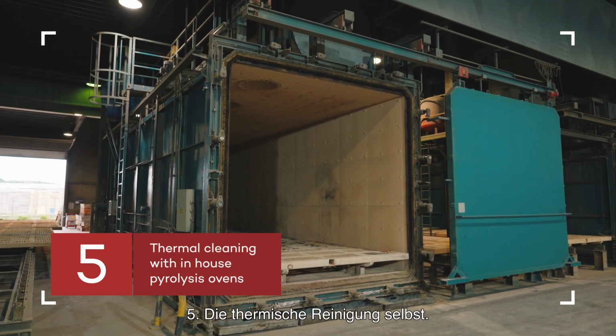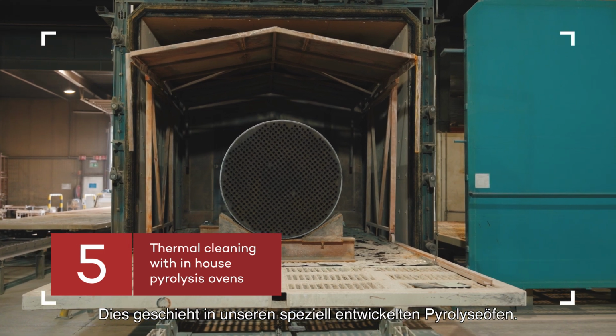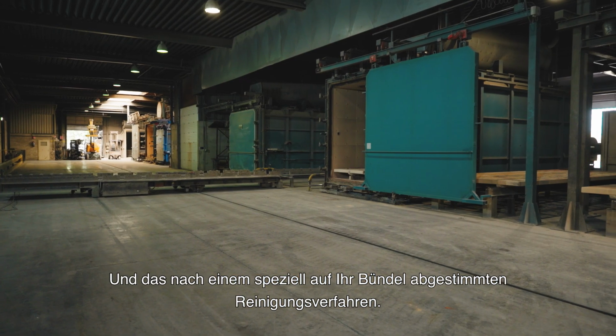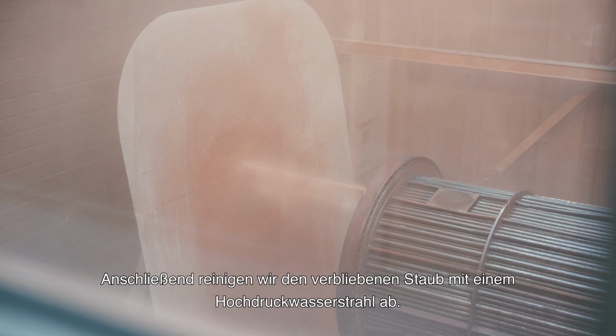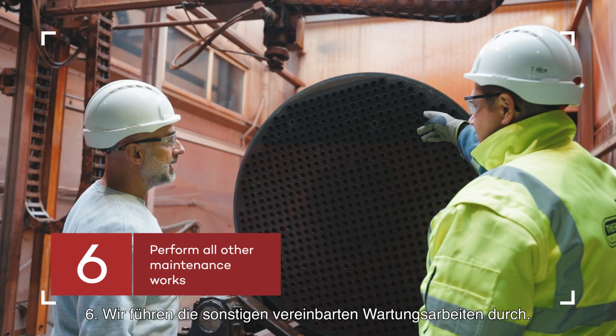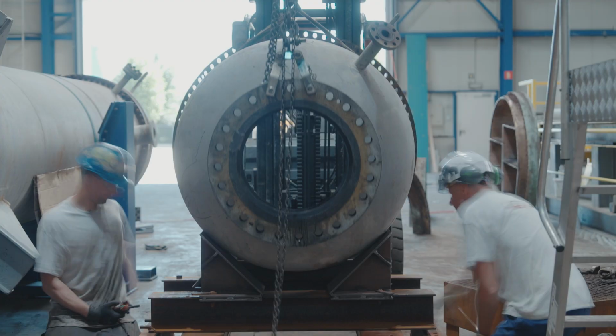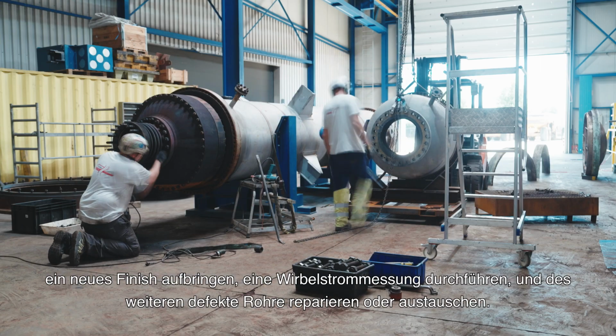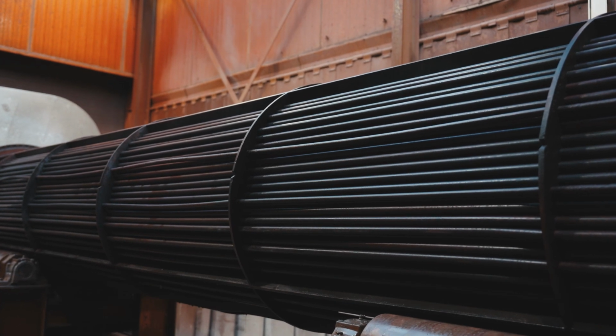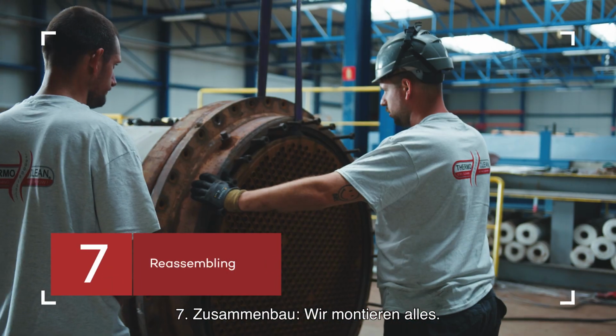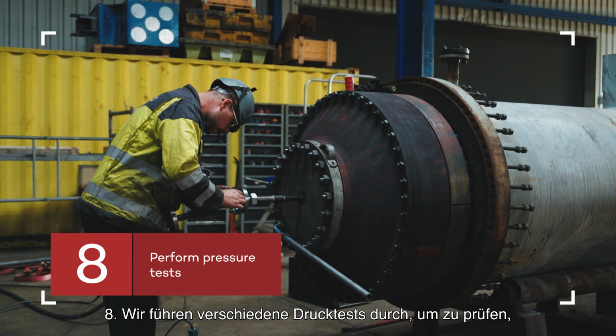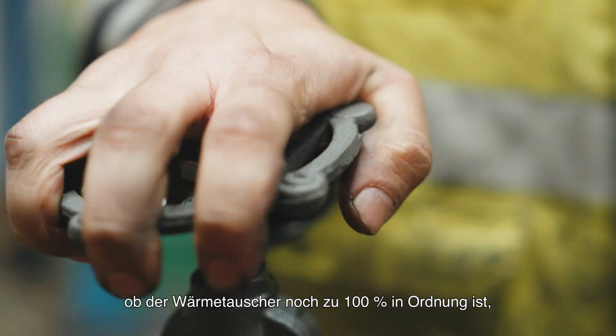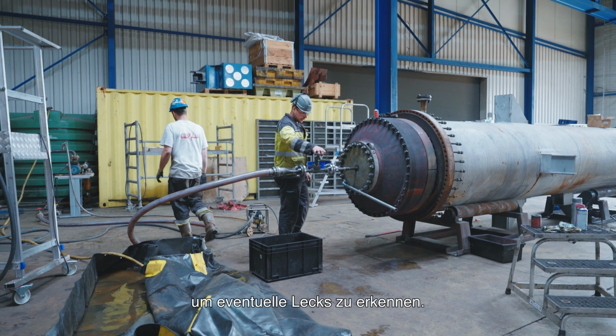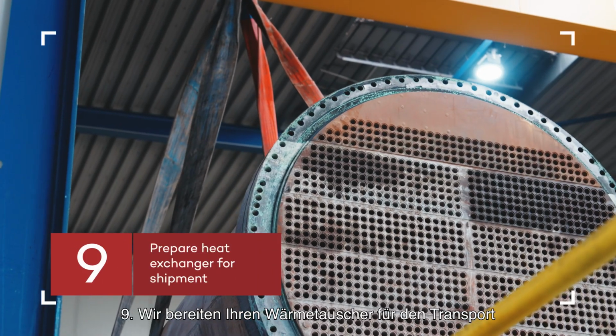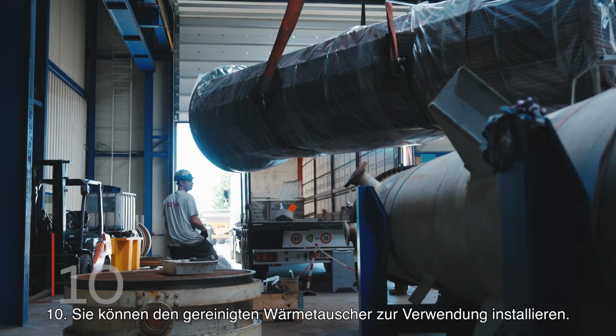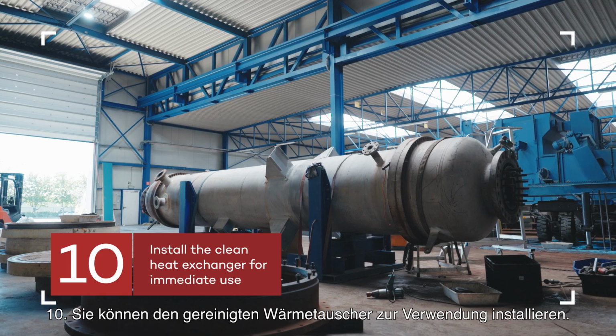5. The thermal cleaning itself is performed in our specially in-house developed pyrolysis ovens and according to a cleaning procedure that is customized to your bundle. After that, we clean off the heat exchanger with high-pressure water jetting. 6. We then perform all the other specified maintenance works. This means that we can refinish the casing, perform an eddy current testing, or even repair or replace damaged tubes. 7. Reassembling. We assemble everything. 8. We perform several pressure tests to verify that your heat exchanger is 100% operational and to detect any potential leakage. 9. We prepare your heat exchanger for shipment and return it to your site. 10. You can install the clean heat exchanger for immediate use.